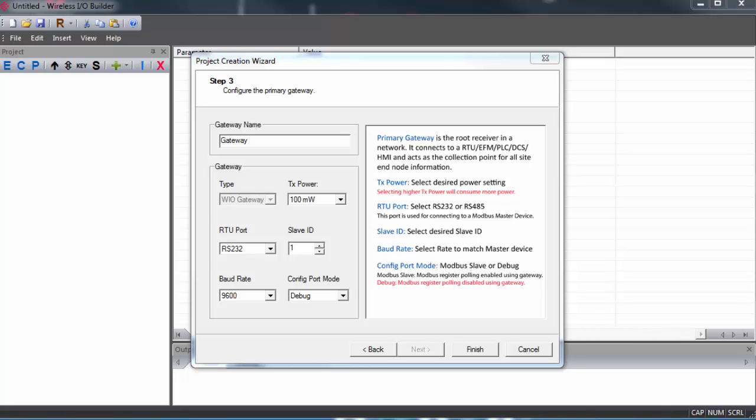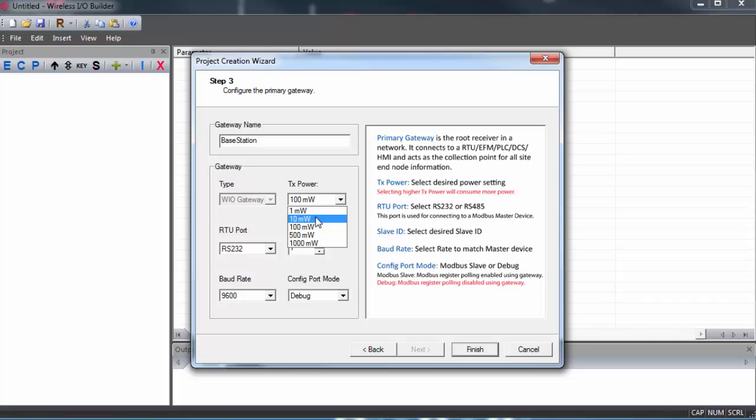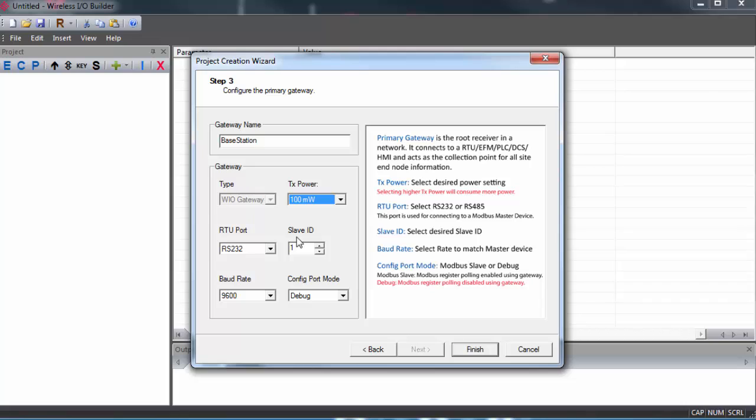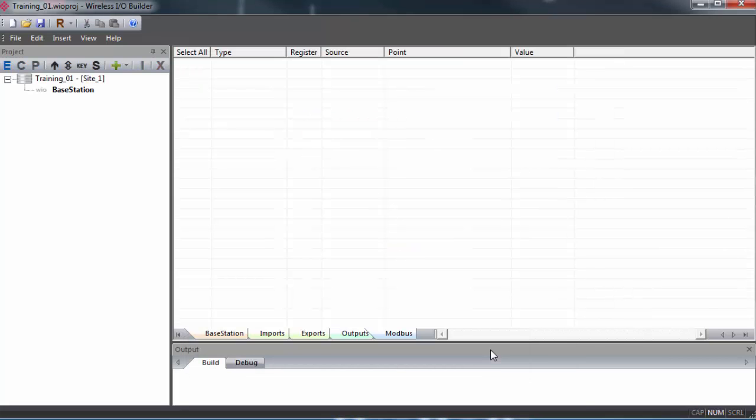Next, we'll configure the primary wireless gateway. We'll give our gateway a name. This is what we'll see inside the project. We can select the power output to the antenna. Be sure to select 10 mW or higher for any sort of real application. And we have our Modbus RTU settings. You only need to concern yourself with this if you're connecting your gateways to third-party Modbus devices. Again, we have another video that covers that configuration. So click Finish, and we'll confirm this.